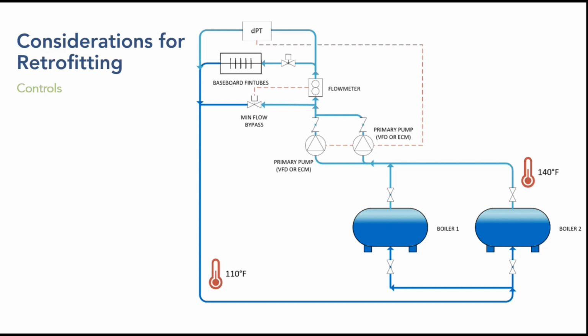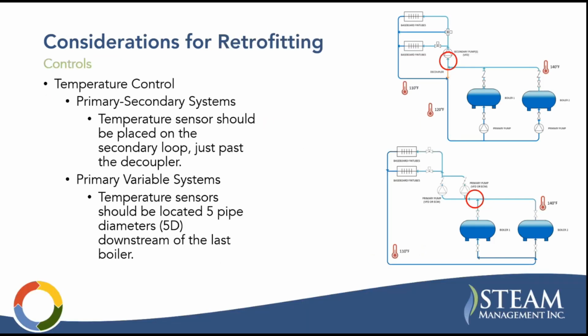Well, I guess in this case, actually, it would be the boiler because your VFD is not going to turn down below the minimum flow through the pumps. Anyway, considerations, temperature control. So on your primary secondary system, you can control to a differential temperature across the system. If you're doing a primary secondary system, you want to locate that on the secondary loop past the decoupler. If you're in a primary variable system, you want to locate it at least 5 diameters downstream of the last boiler in the system if it's multiple boilers.